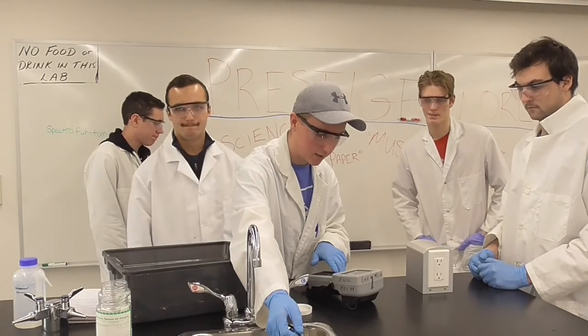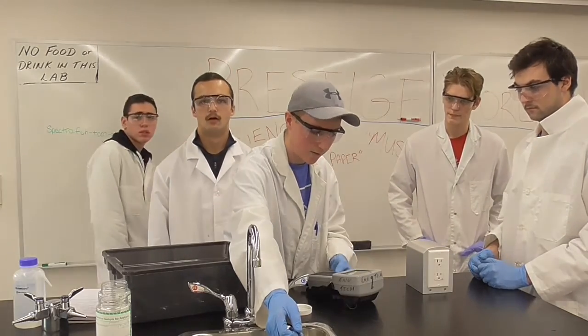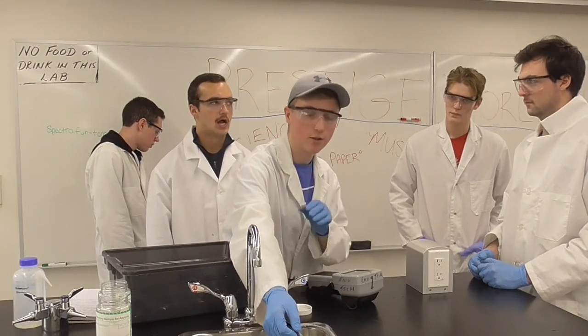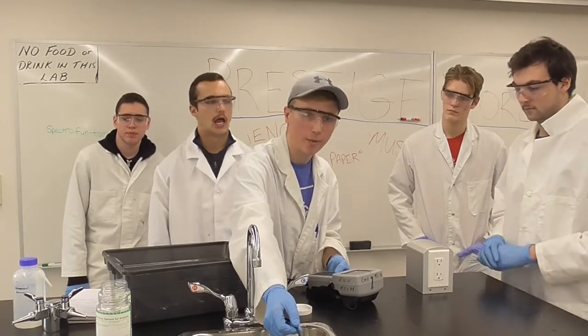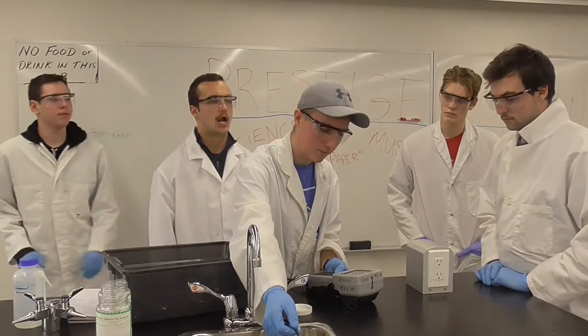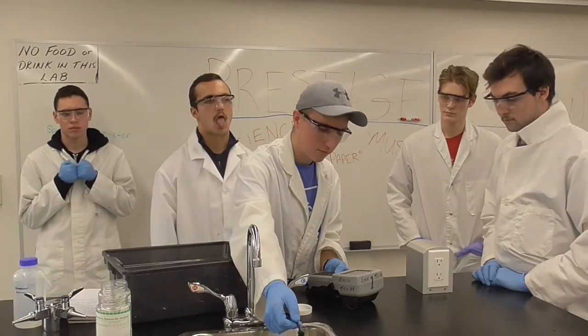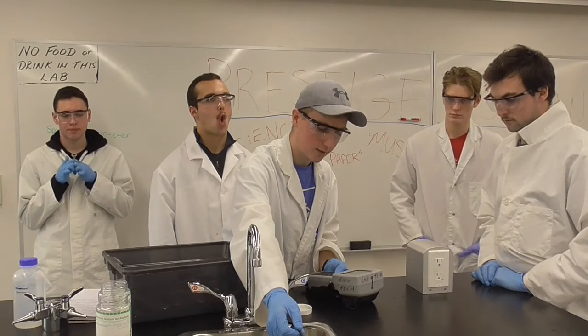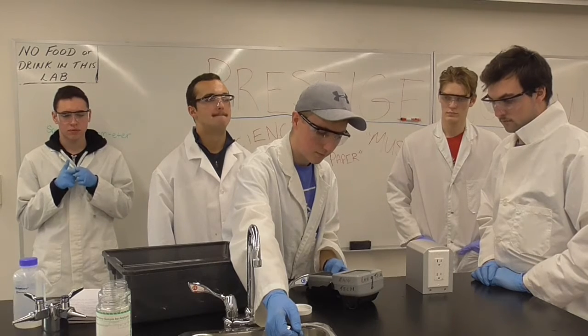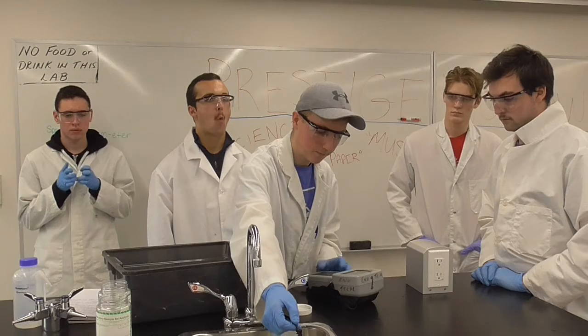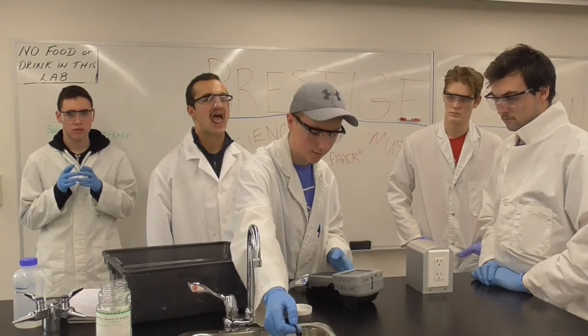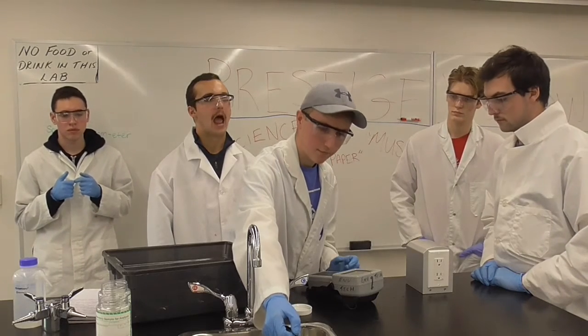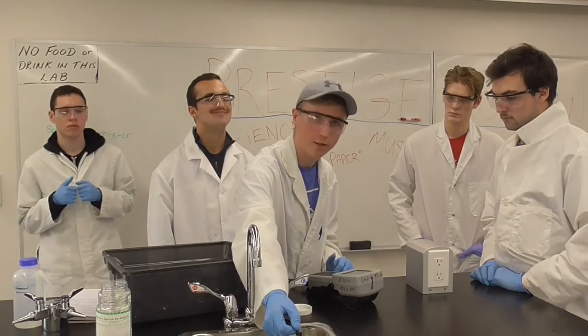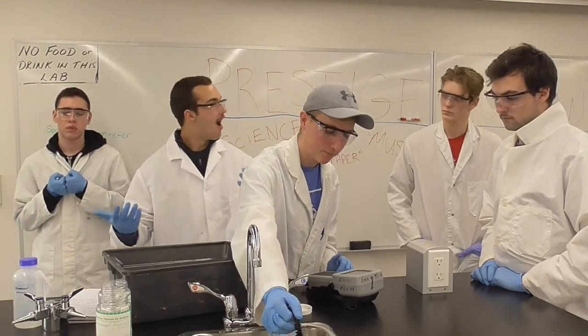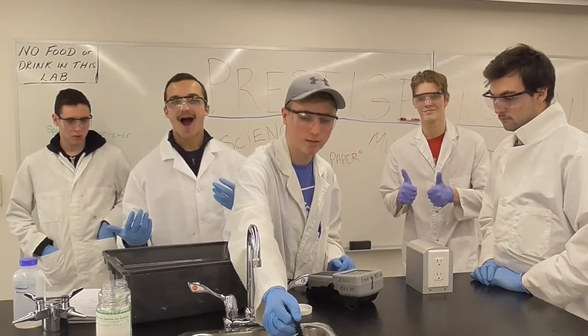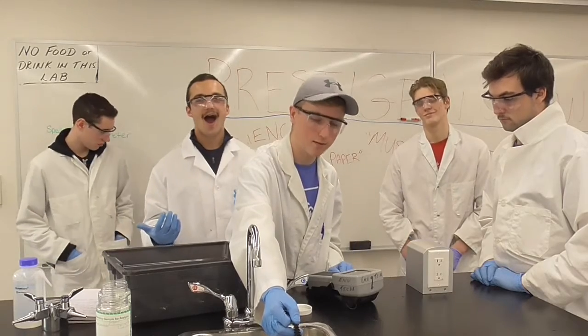for milligrams per liter. And hit enter. And now, from the titration, we know that the dissolved oxygen in this tap water is 9.2 milligrams per liter, so I'm going to hit the up arrow and get to our desired amount. So almost there. Gonna hit enter, and we're calibrated now. So I'm gonna hit mode, and we're reading 9.21 milligrams per liter for dissolved oxygen in this sample, and that's what we want. So that's good. Also, the temperature is 20.0 degrees Celsius. So yeah, that's it.